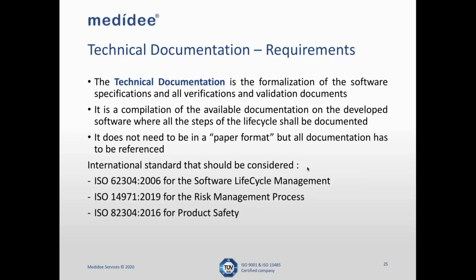Now the software standards that you want to consider. The 62304 is a standard that is going to define to some extent a state of the art. This can be debated, but this is basically defining the different steps for the software lifecycle management, from the assembly of the requirements all the way down to the verification and validation, and the release of the software. Again, the 14971 is going to be useful to address the risk aspects, which are also covered in the 62304. And another standard which is useful to take into consideration is the 82304, which basically completes the 62304 by expanding the scope of the design process. So when you want to implement a design process and a lifecycle management process that is compliant with the regulation, you want to have a look at these different standards.